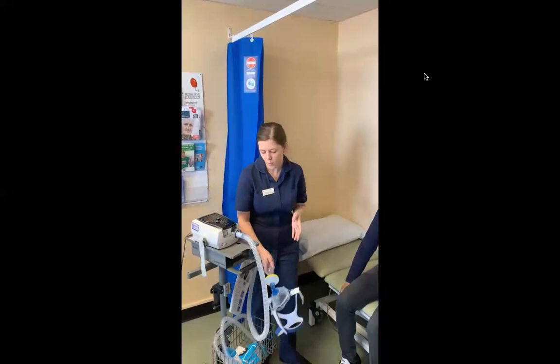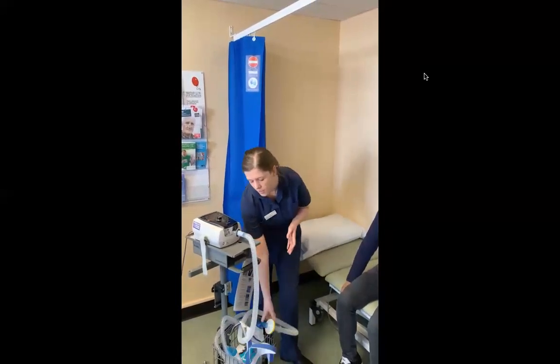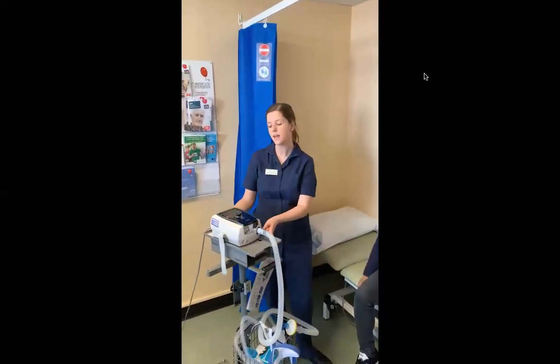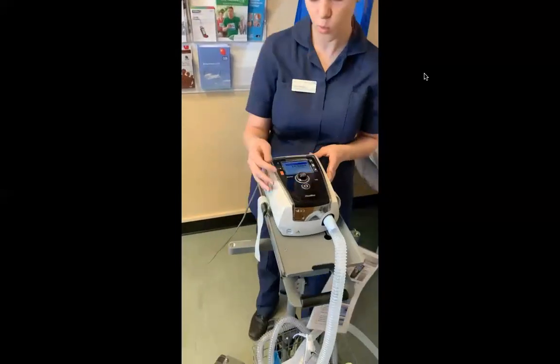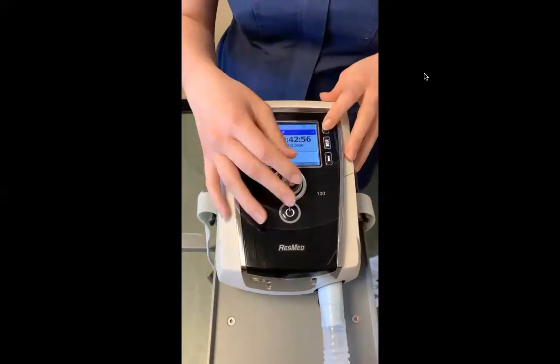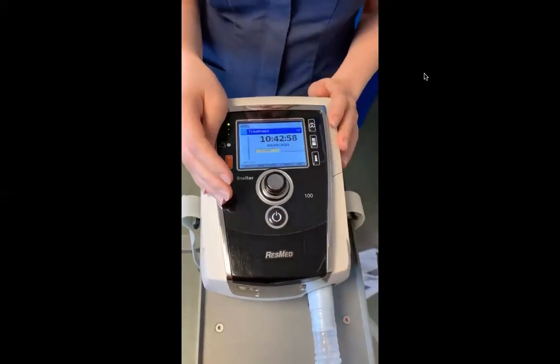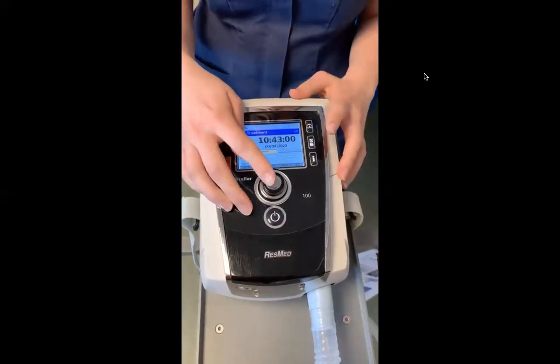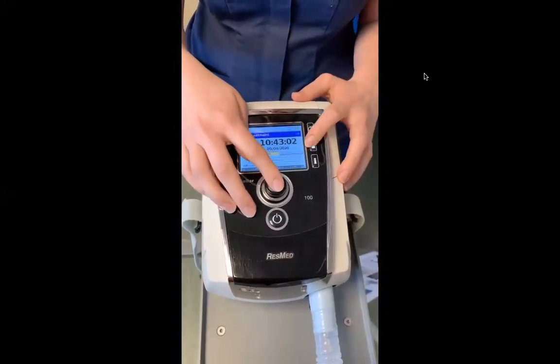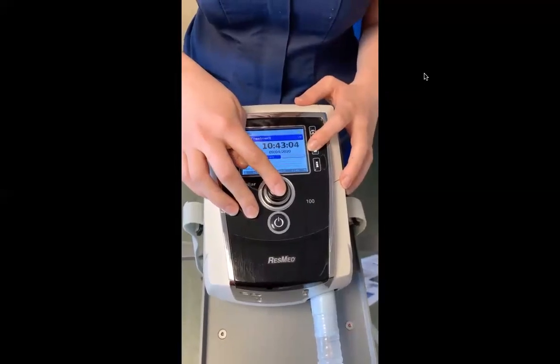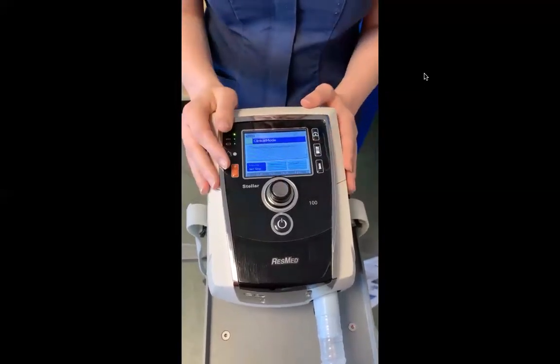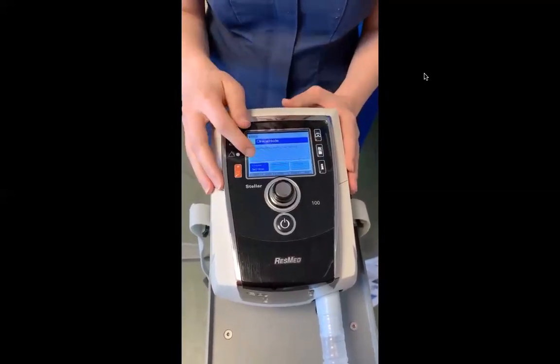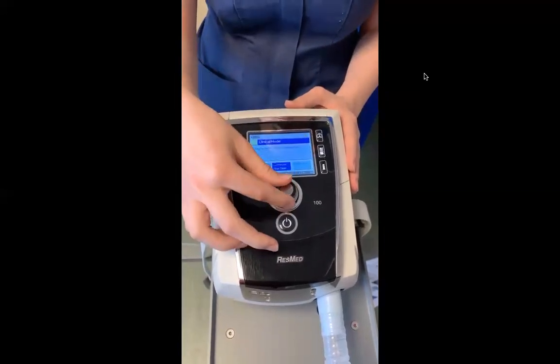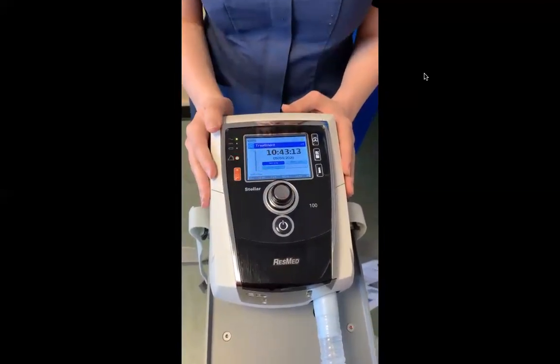So first of all, we turn the machine on. Now I'm going to show you how to do your learn circuit. A learn circuit is really important because it enables us to check that the machine is safe. First of all, you come to this screen and you're going to unlock. You press the middle button and the 2 ticks and you hold down for 3 seconds. It's really good to make sure you only unlock for 5 minutes because you want to make sure the machine is locking again and that it's safe. That way no one can adjust your settings.